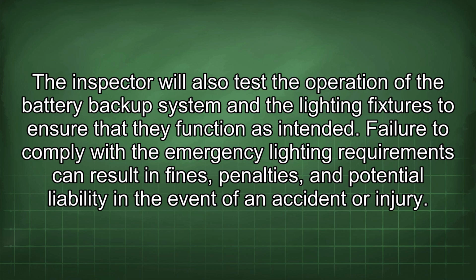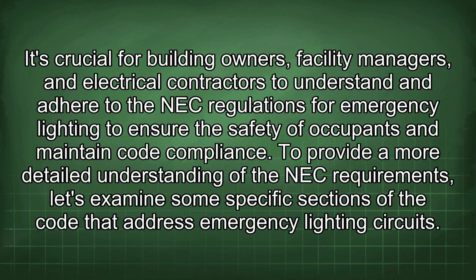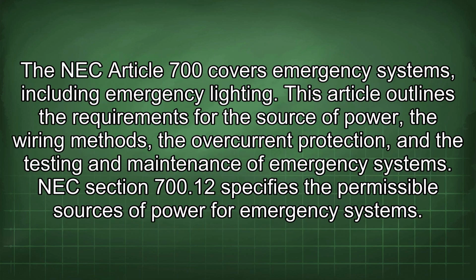Failure to comply with the emergency lighting requirements can result in fines, penalties, and potential liability in the event of an accident or injury. It's crucial for building owners, facility managers, and electrical contractors to understand and adhere to the NEC regulations for emergency lighting to ensure the safety of occupants and maintain code compliance. To provide a more detailed understanding of the NEC requirements, let's examine some specific sections of the code that address emergency lighting circuits. The NEC Article 700 covers emergency systems, including emergency lighting.